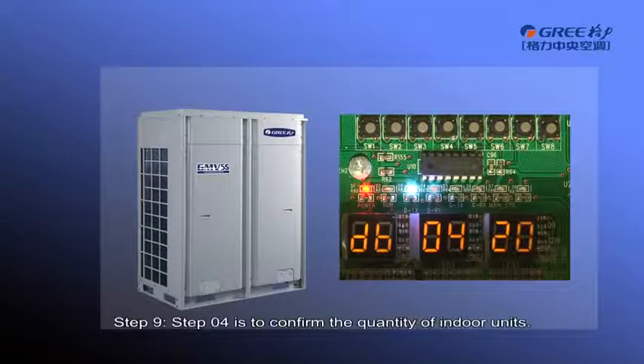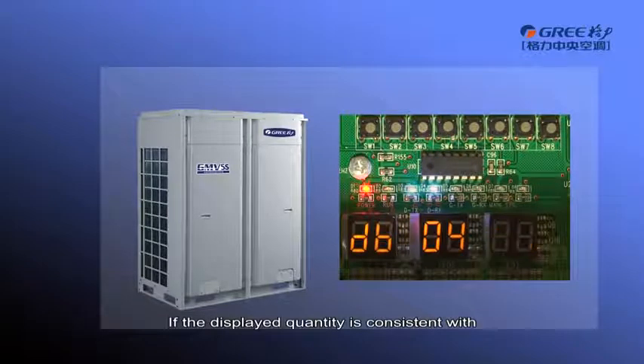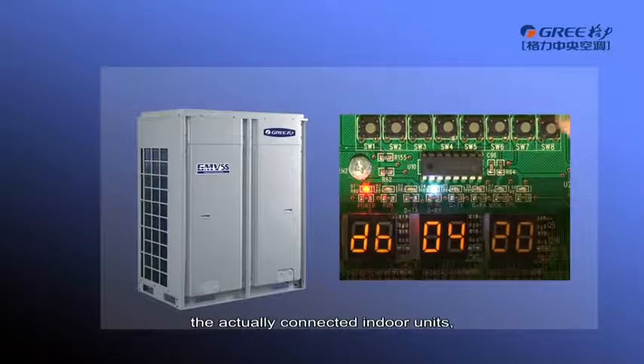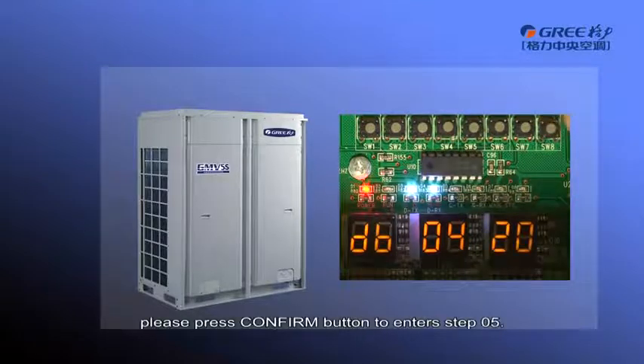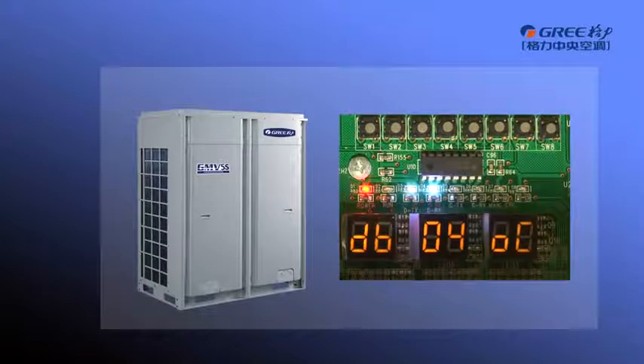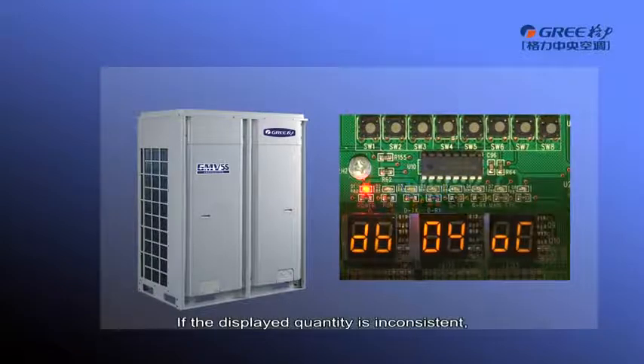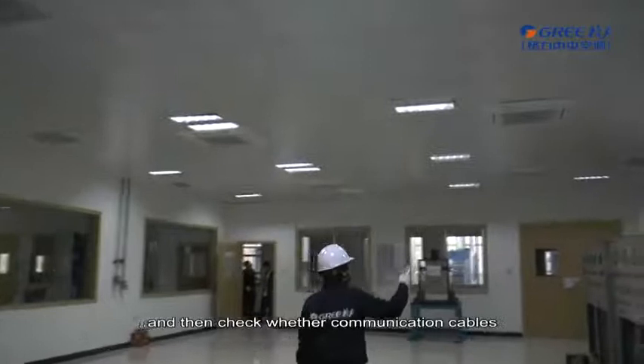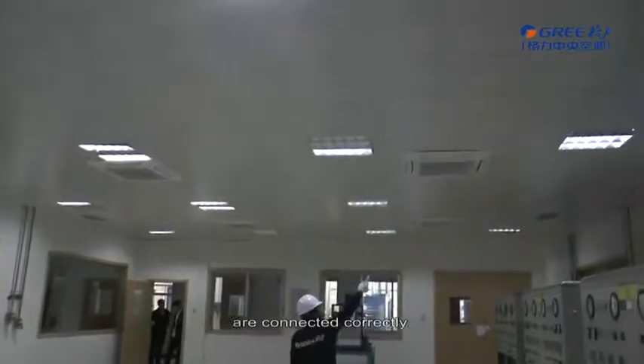Step 9. Step 4 is to confirm the quantity of indoor units. If the display quantity is consistent with the actually connected indoor units, please press Confirm button to enter Step 5. If the display quantity is inconsistent, please check whether each indoor unit is power on and then check whether communication cables are connected correctly.